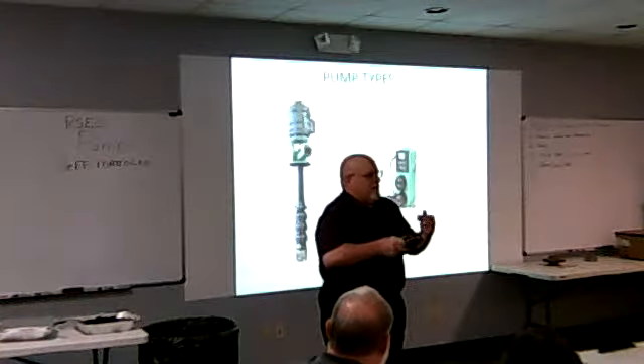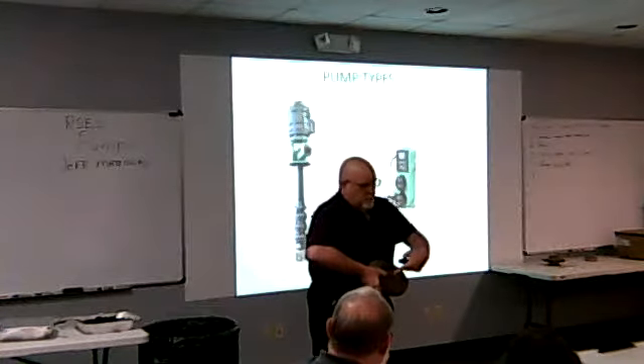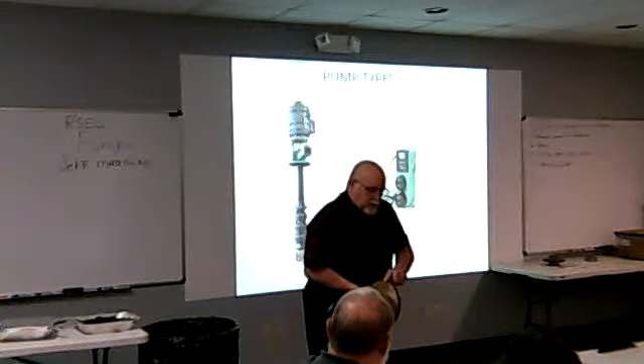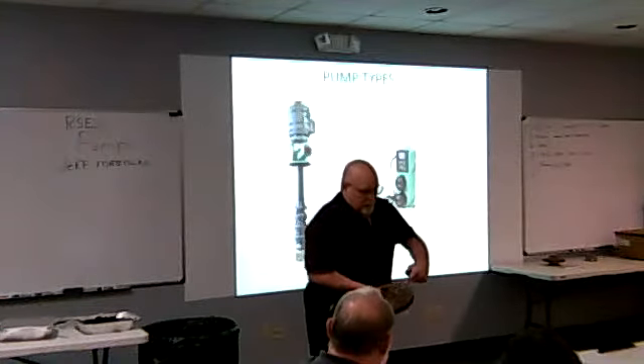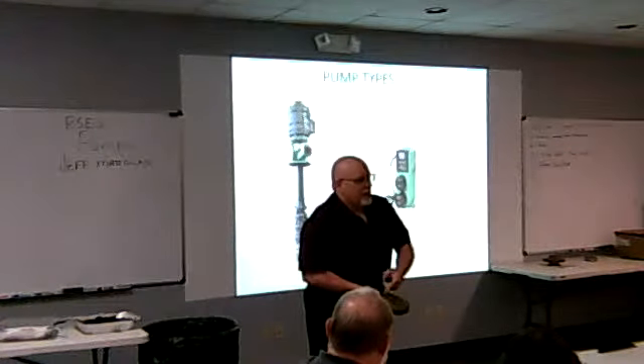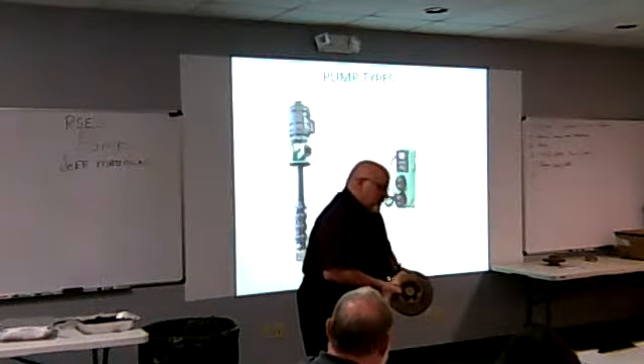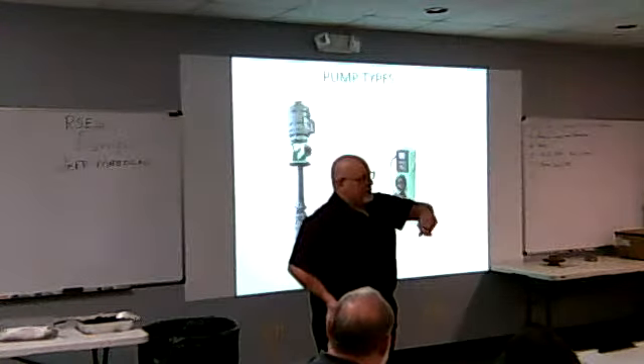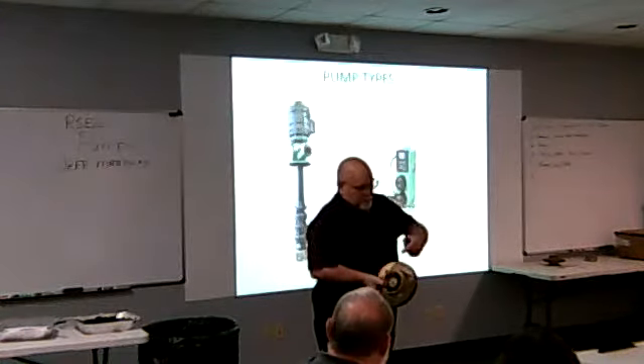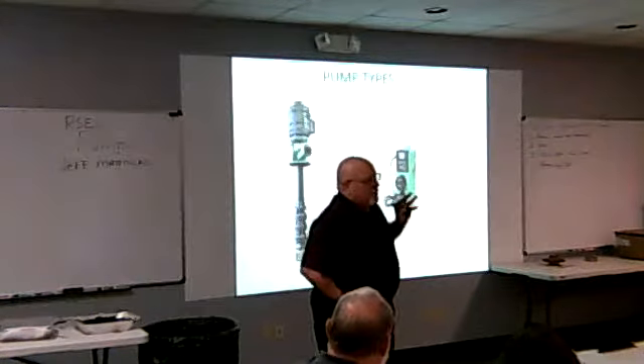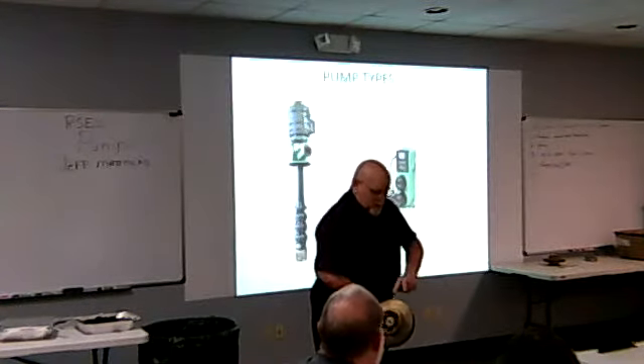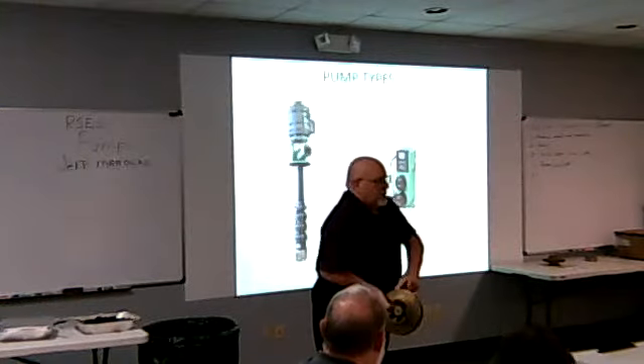This is called a Francis vane impeller. The water goes in here. As this turns, you'll see that these are curved. These are actually curved in here like this. And as it spins, the water gets forced with that spin up to the cutwater of the pump, which is the port of the pump here. As it spins, it forces the water up and out. You can see in here they're curved. You'll see when it spins.